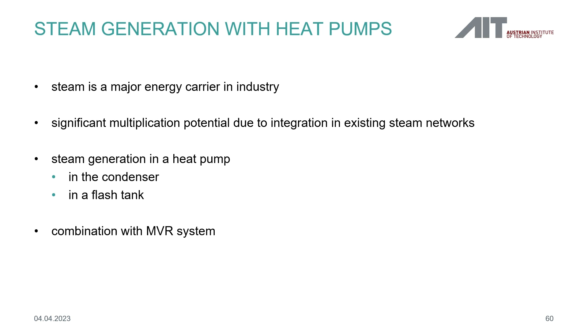The first example is the Bamboo project. It's another Horizon 2020 project where we did a lot of work on steam generation with a heat pump and a flash tank. On this photograph, you see the installation that was set up in the lab of EDF in France. On the left, there's the heat pump. It's a water-to-water heat pump operated on a synthetic refrigerant, R1336mzz(Z), that produces pressurized water. That pressurized water is then used in a flash tank unit that was especially designed for this purpose. There steam is produced by reducing the pressure of the pressurized water. So part of the water is evaporated, and the steam can be used for further application.